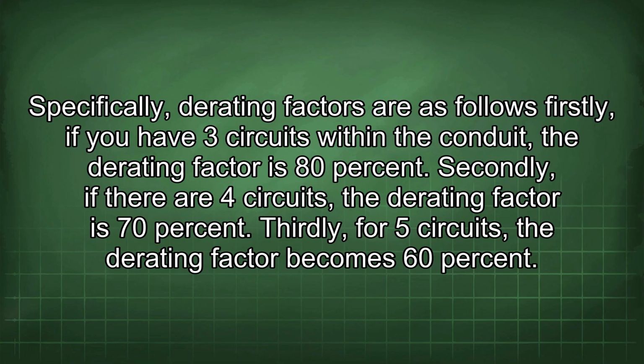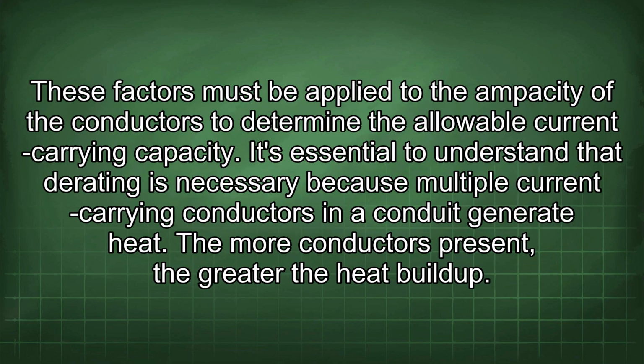Firstly, if you have 3 circuits within the conduit, the derating factor is 80%. Secondly, if there are 4 circuits, the derating factor is 70%. Thirdly, for 5 circuits, the derating factor becomes 60%. These factors must be applied to the ampacity of the conductors to determine the allowable current carrying capacity.